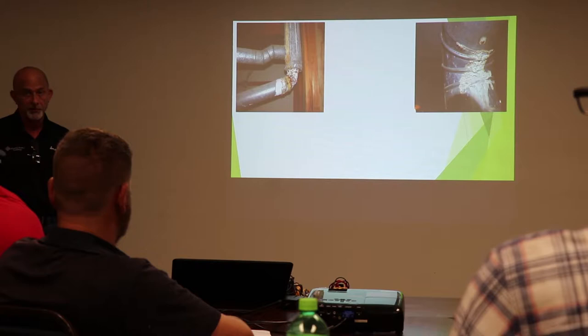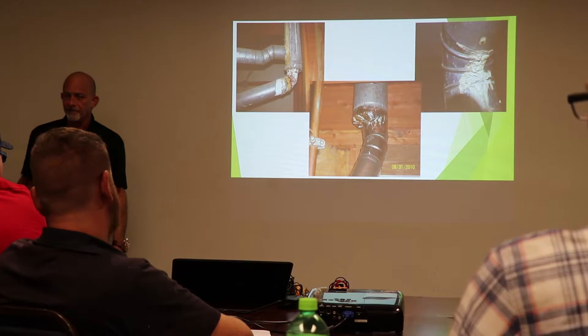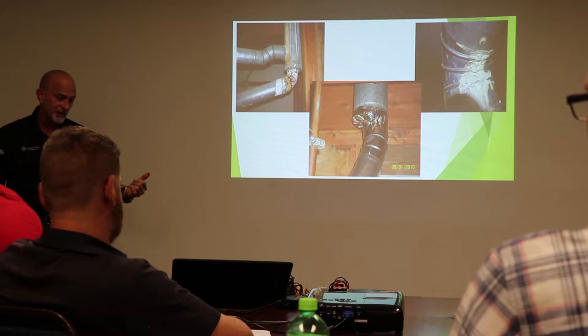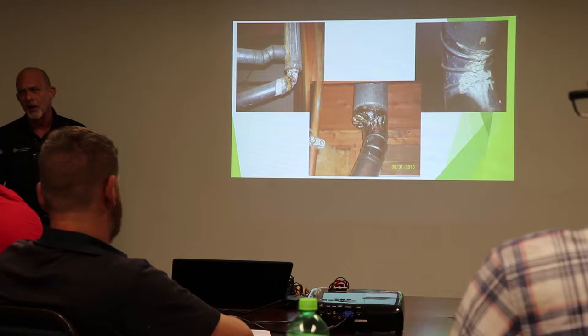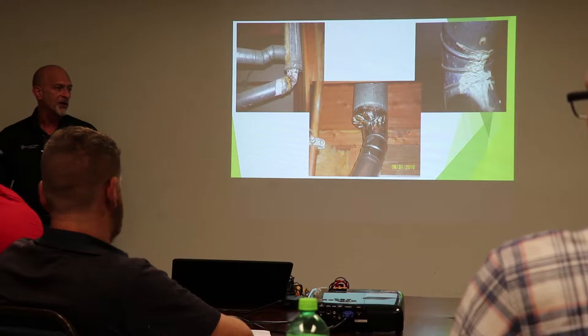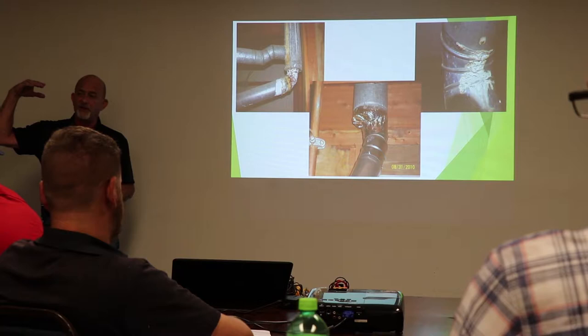Or you might see something like that when you're looking at your vent pipe. It happens, guys. It's out there. I've also seen 80% furnaces trying to be vented out with PVC. It does last a little while till it melts. On a 90-plus furnace, we want to check for any horizontal runs in our PVC. From my experience, I see a lot of PVC out there that's not supported enough. It starts bellying down.